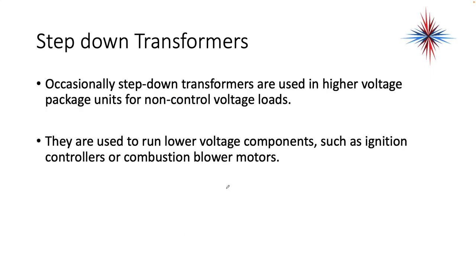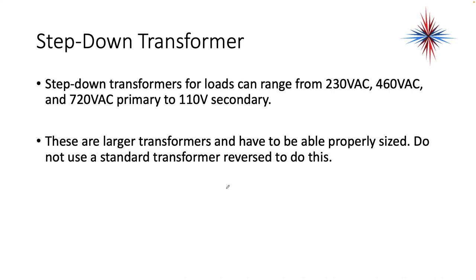Occasionally, step-down transformers are used in higher-voltage package units for non-control voltage loads. They're often used to run lower-voltage components such as ignition controllers or combustion blower motors — that's where I see them most frequently, in combustion blower motors in gas rooftop units. The combustion blower motor is maybe a 110 or 120-volt motor, while the rooftop unit is a 480-volt system, so we use a step-down transformer to get from one to the other. Step-down transformers for loads can range from 230, 460, and 720 primary to 110 volts secondary. These are larger transformers and have to be properly sized — do not use a standard transformer to do this.